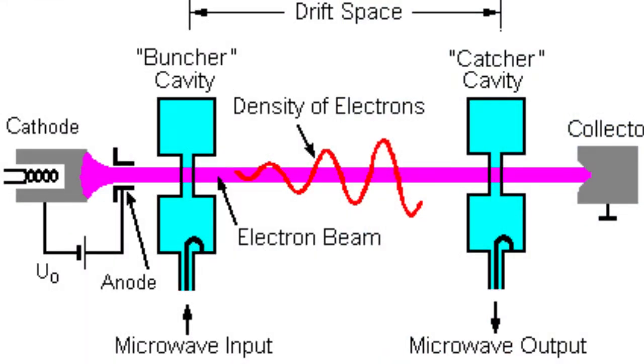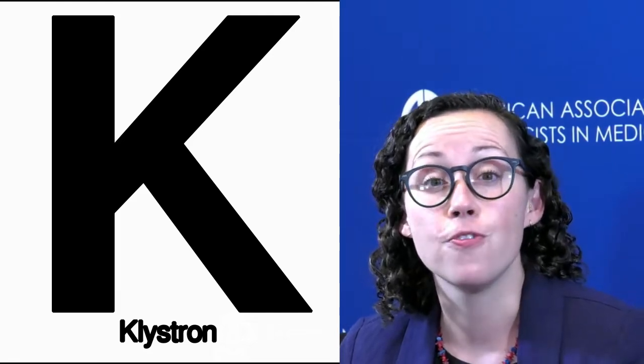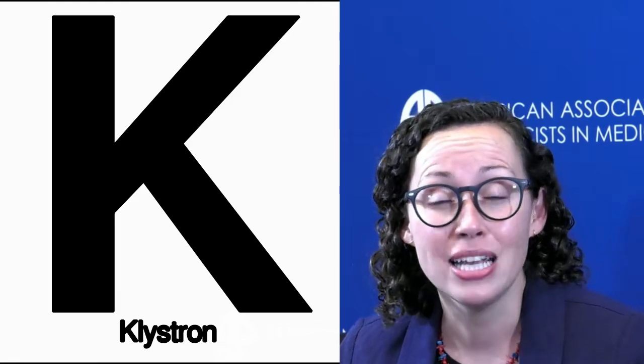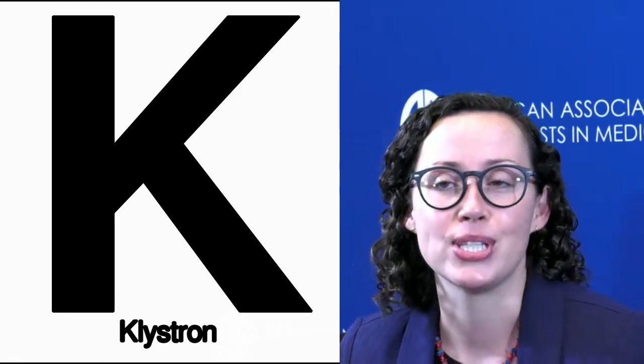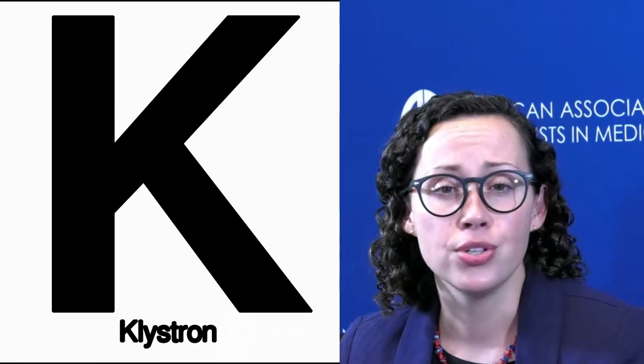K is for Klystron. A klystron is an essential part of a medical linear accelerator. It is one type of device that provides microwave power that the linear accelerator needs to generate radiation for treating cancers. Modern clinical radiation therapy linear accelerators need microwave frequencies that are very high, about 3 billion cycles per second. Klystrons are used in many types of linear accelerators today.